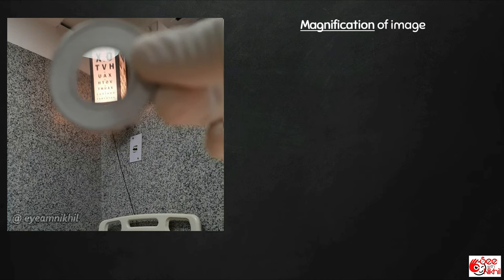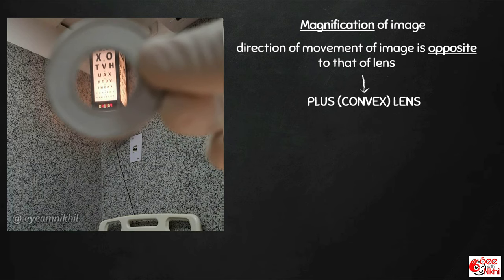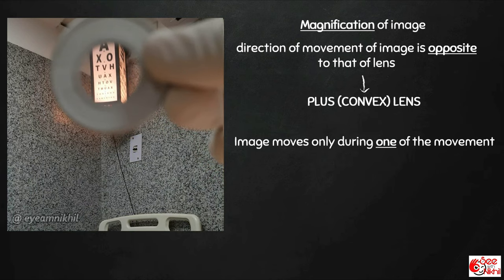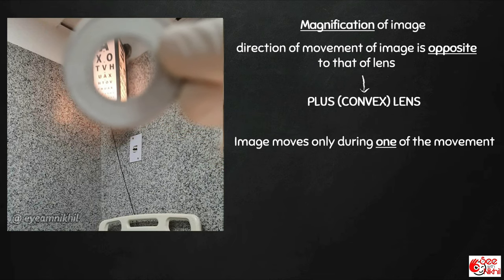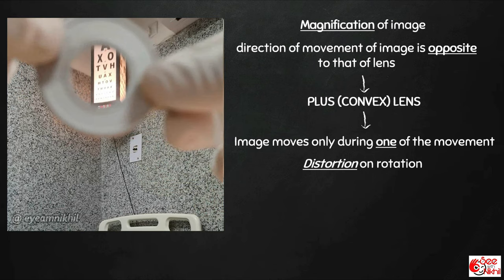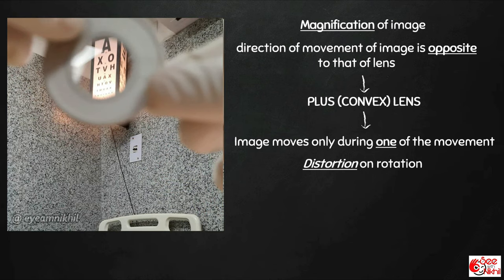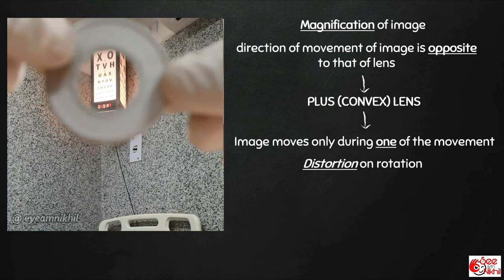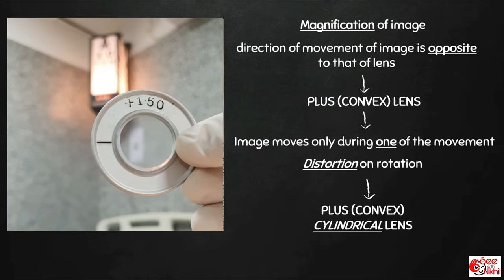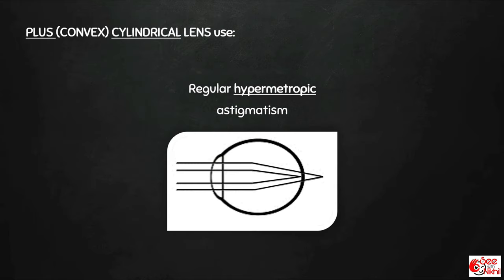Looking at the second lens: there appears to be a slight magnification of image, and movement of the image is in the opposite direction, which means it is a plus lens. The image moves only during vertical movement but not horizontal — that is, it moves only during one of the movements. There is also distortion on rotation, so this is a plus cylindrical lens. Cylindrical lenses are used for correction of astigmatism; a plus cylindrical lens is used in correction of regular hypermetropic astigmatism.